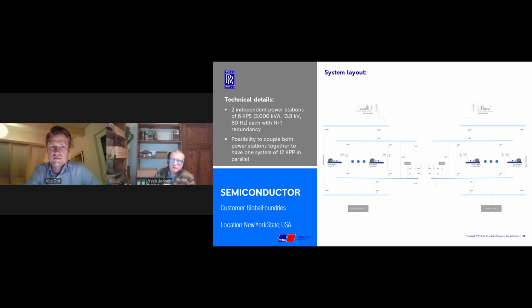So as I mentioned before, the challenge when we place parallel systems into parallel is the fault level. That challenge could be solved with an IP bus, as I just mentioned, with a choke to reduce the fault level contribution of each machine, or to work in medium voltage. So here we chose the second solution. We work in medium voltage. We could have a low voltage alternator with a step-up transformer, or we could have directly a medium voltage alternator. So this is the configuration that we have at Global Foundries.